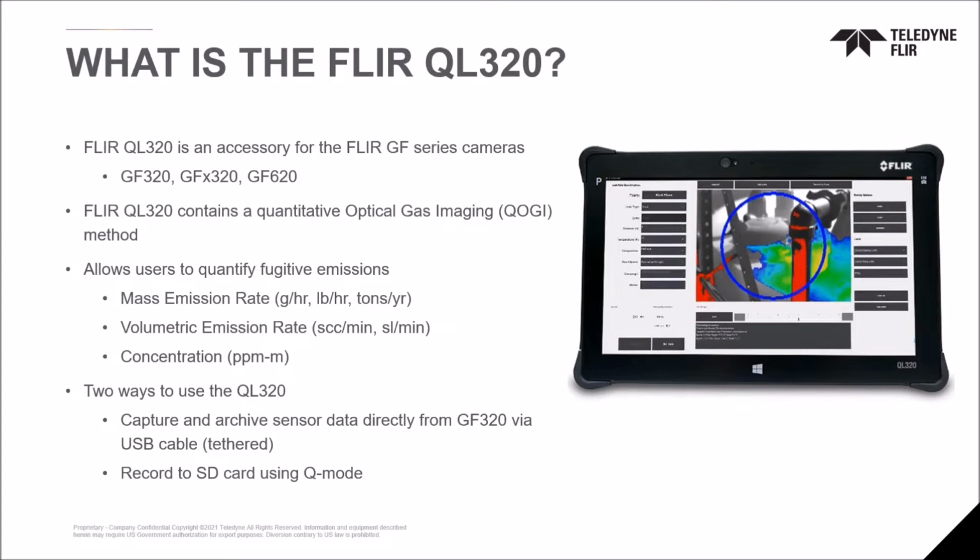There are some advantages in that, and we'll talk a little bit about those, but it does require a little bit more cumbersome use while you're in the field because you're tethering in, and you cannot use this device in a Class 1 Division 2 or a Zone 2 location.